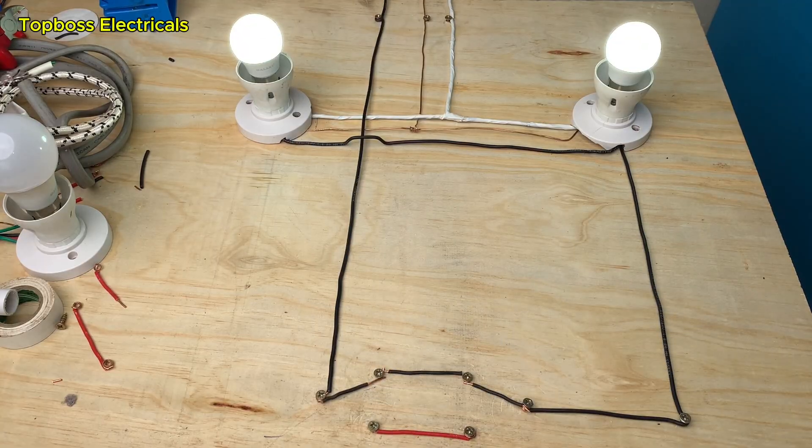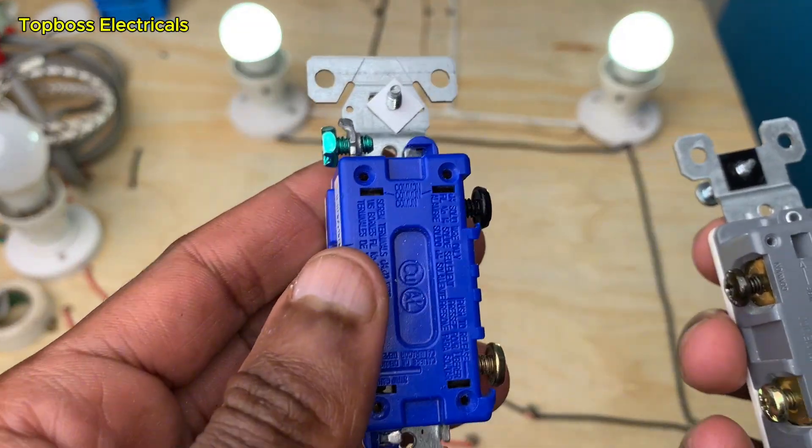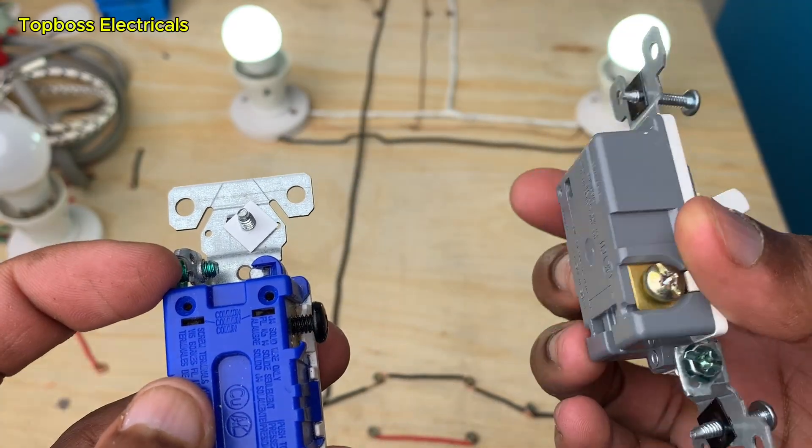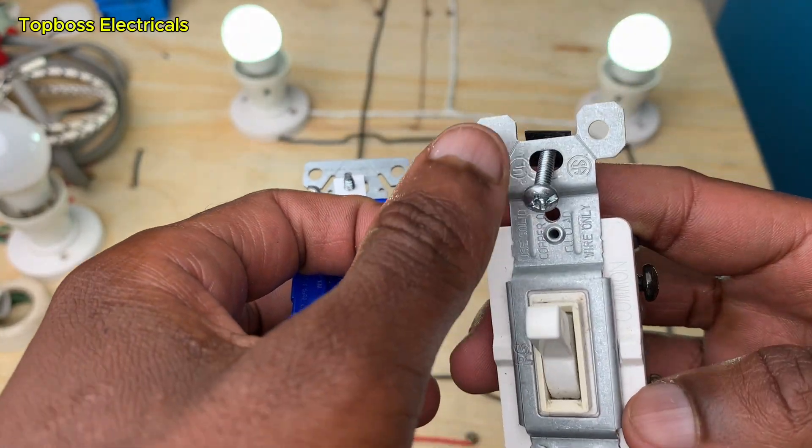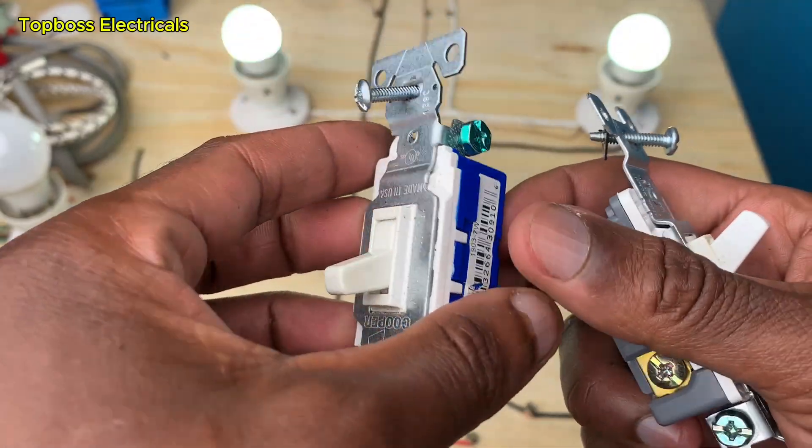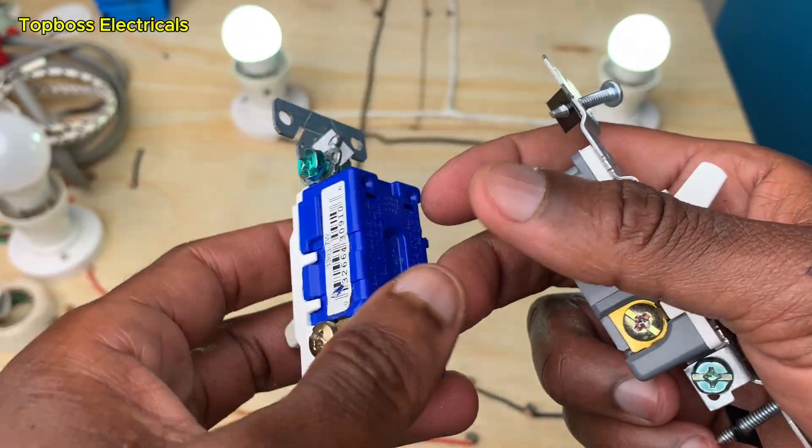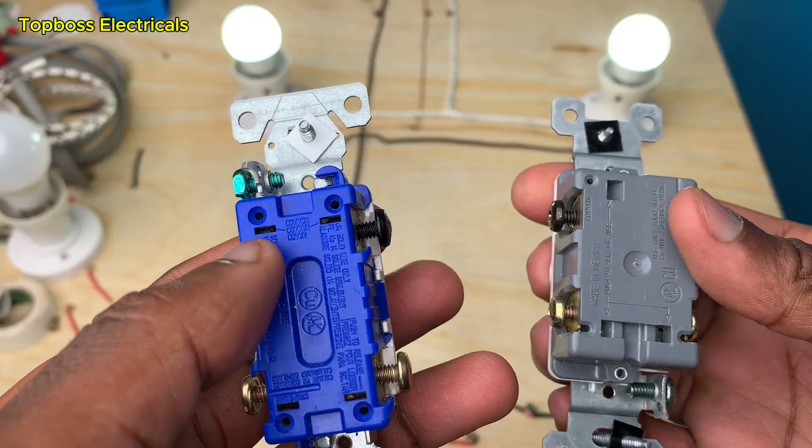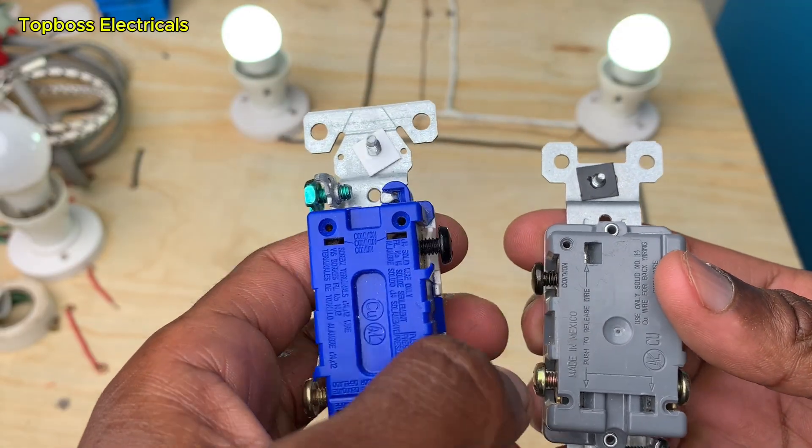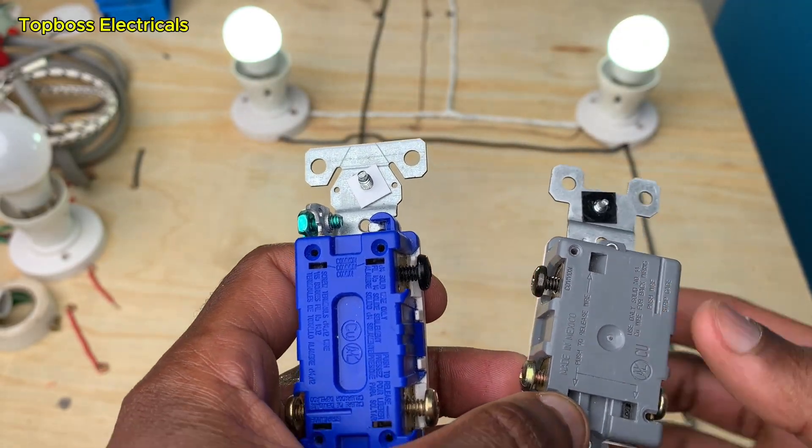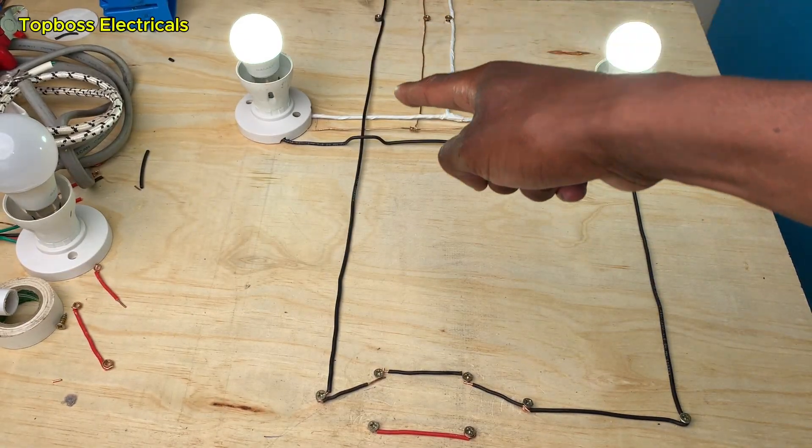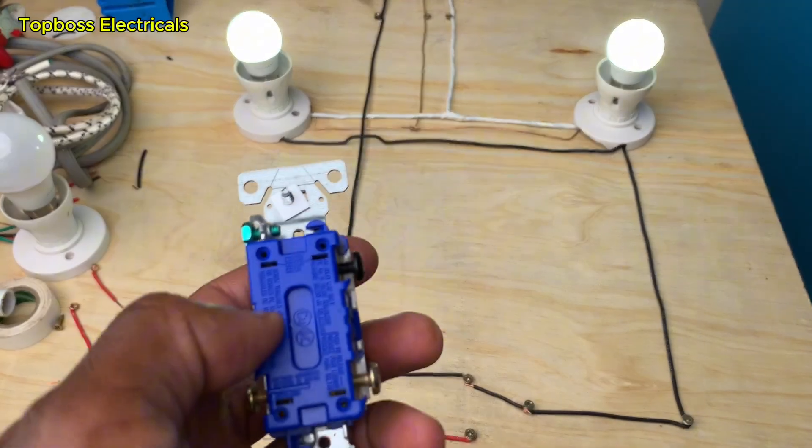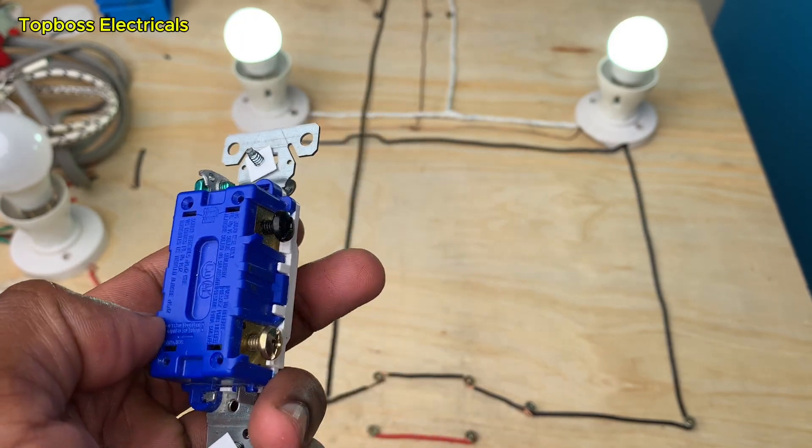We'll have the ground wire connected here, and you can see that the ground wire is in touch with the entire metallic part of the switch. Then we have the common, which is very important for our case. The common for this switch comes all the way from the feed and gets to the common of this switch right here.